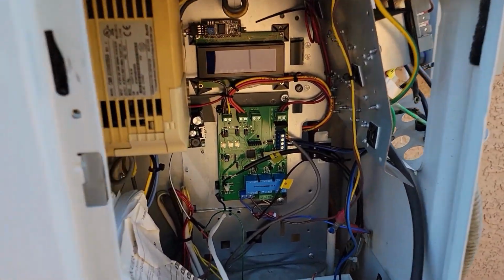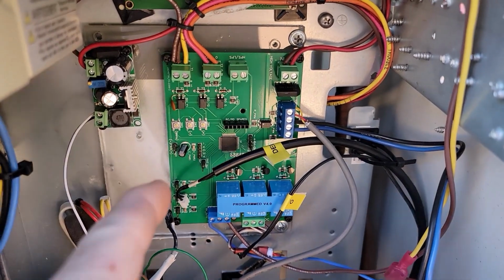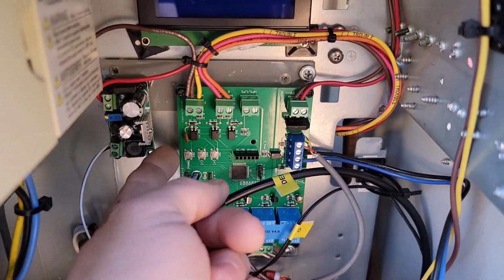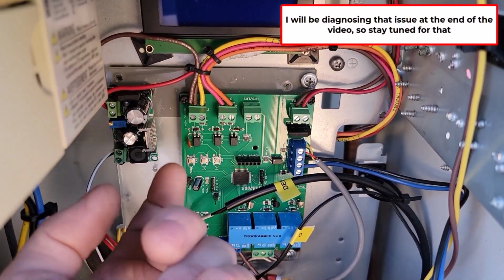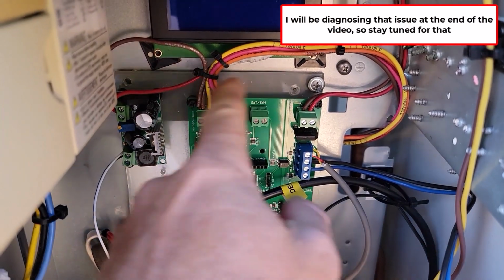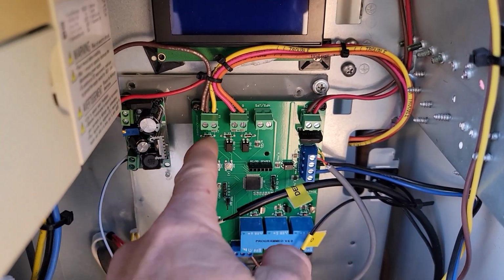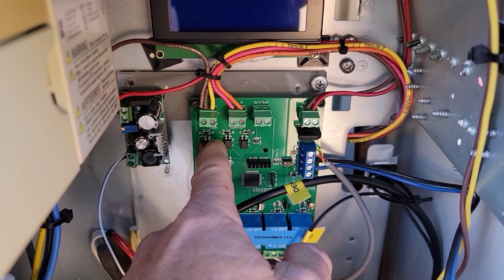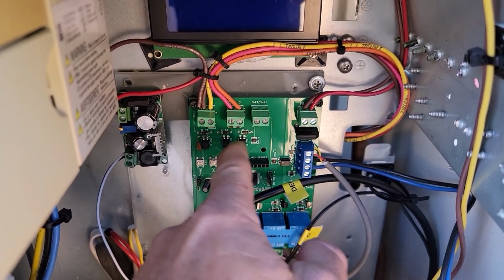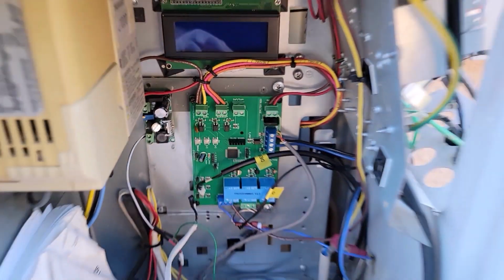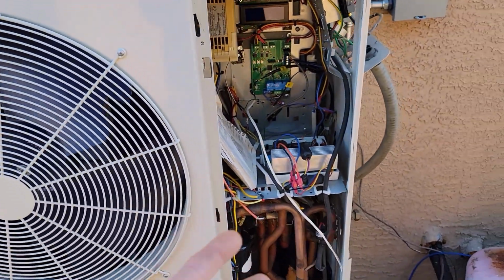The sun went down, and I think I realized what happened is one of these connections is loose, or the solder joint to the capacitors on the back for the filtering, for the 24 volts AC to get rectified and cleaned up, and then to DC to hold on each optical isolator to bring on a logical input for Y1, Y2, O, for the reversing valve, which are all these connections right here.